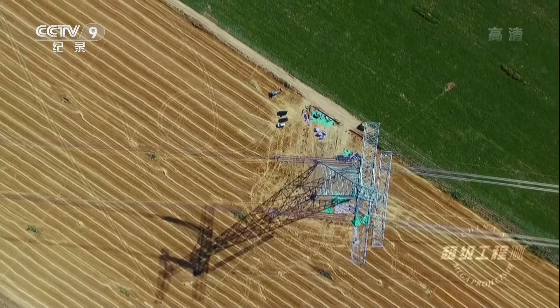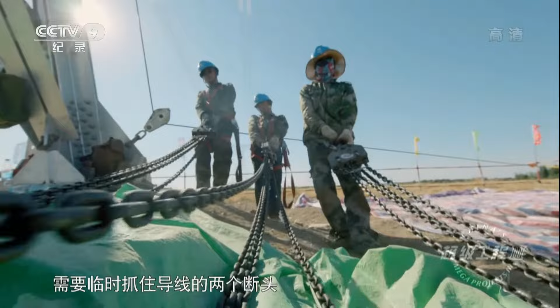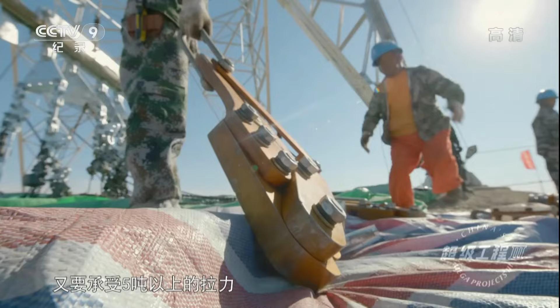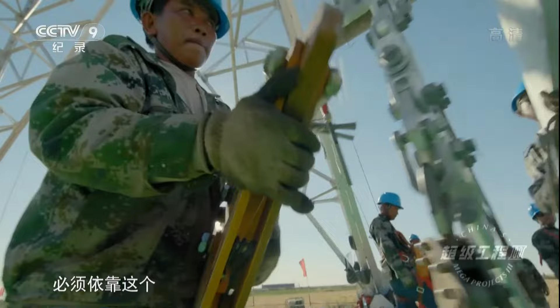The procedure seems simple enough, but it's quite another thing to do it 100 meters up in the air. With everything swaying in the breeze, the workers need to hold two ends of the cables carefully and avoid damaging the conductors while dealing with the 5-ton tensile drag on the cable. To manage this, they must use a special cable clamp.